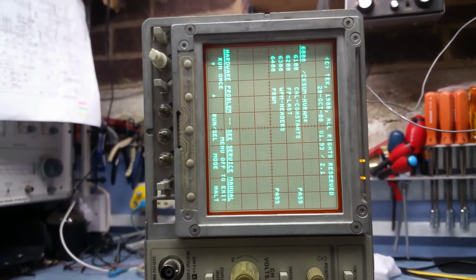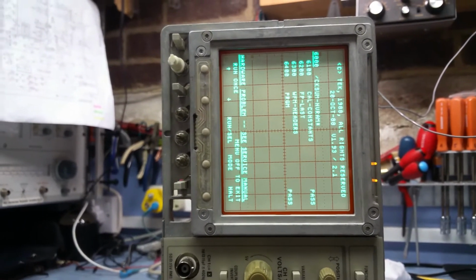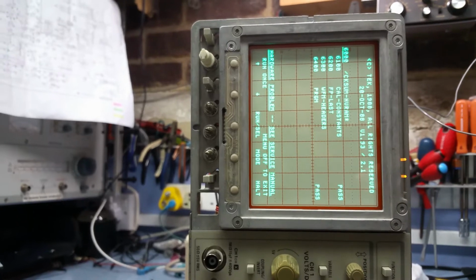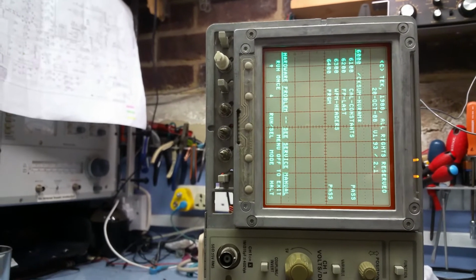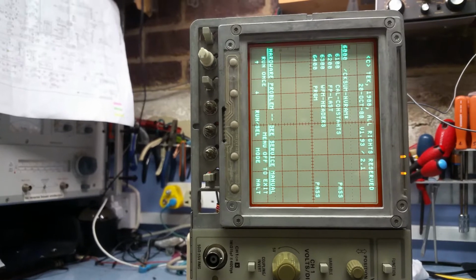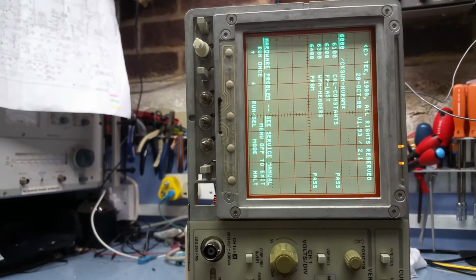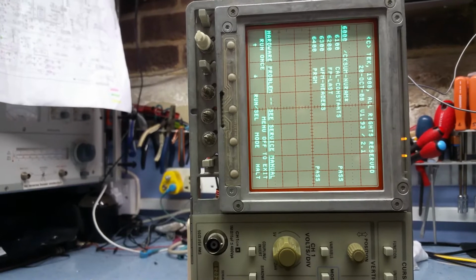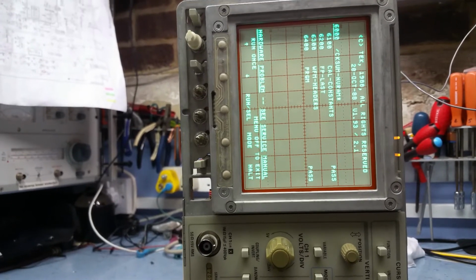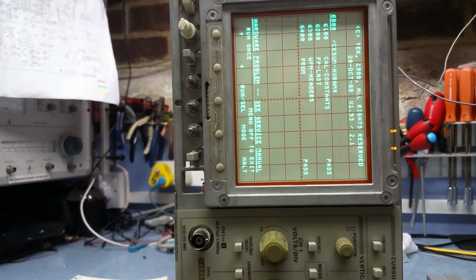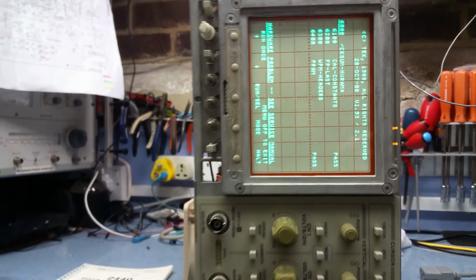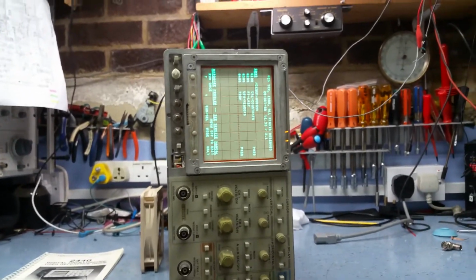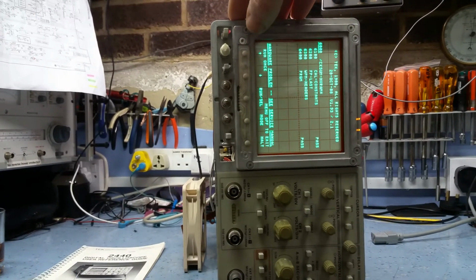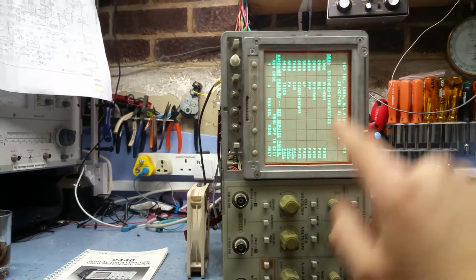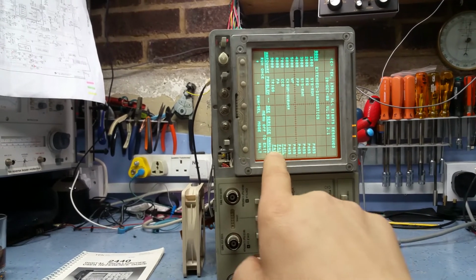So it actually now looks like there's an NVR problem, a memory problem, memory address problem, possibly even a corrupted EEPROM or something like that. So this is going to be the next path of investigation, the memory side of the thing. Now I haven't got the service manual here, but I'm going to go through the service manual and see what it says about this error. Now it's strange because it's not obvious when you're on the previous screen. If you go back to the previous screen, it looks like that's passed. You just look along here, pass, and these have failed here.